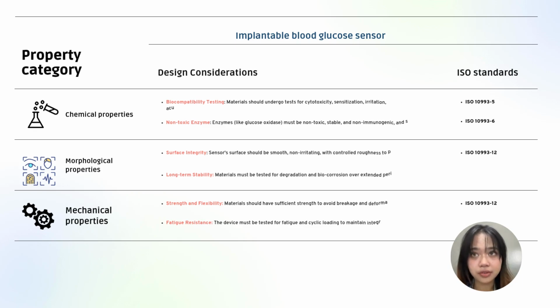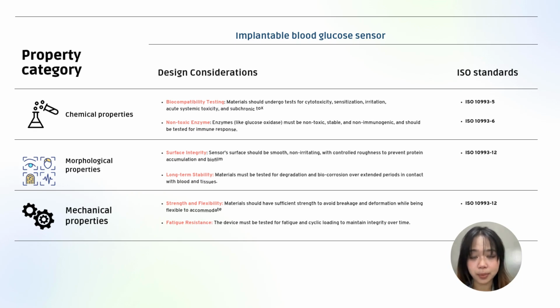Okay, so next I would like to explain the implantable blood glucose sensor by property category. The first category is chemical properties. The design consideration is biocompatibility testing. Materials should undergo tests for cytotoxicity, sensitization, irritation, acute systemic toxicity, and subchronic toxicity. It is based on ISO 10993-5. Next is the non-toxic enzyme. Enzymes like glucose oxidase must be non-toxic, stable, and non-immunogenic, and should be tested for immune response. It is based on ISO 10993-6.